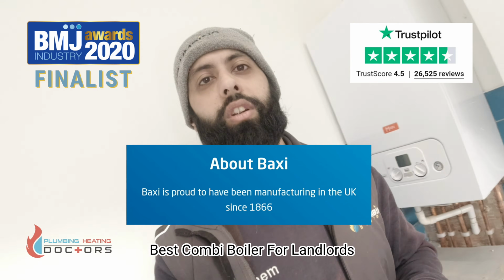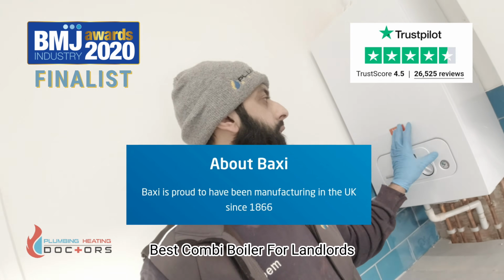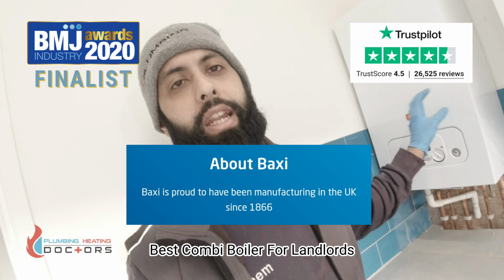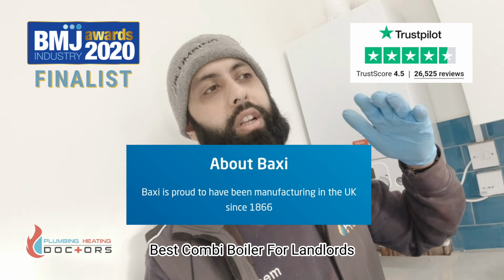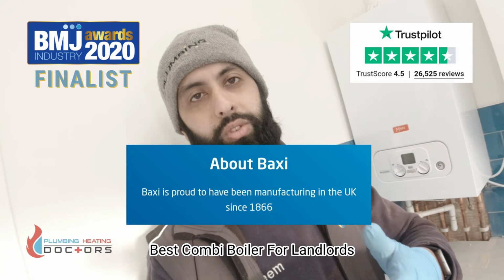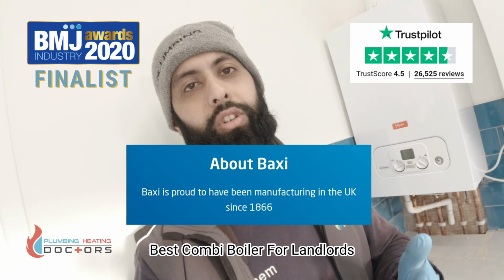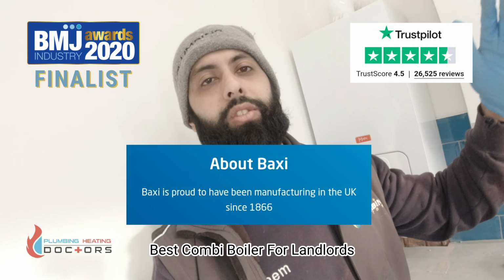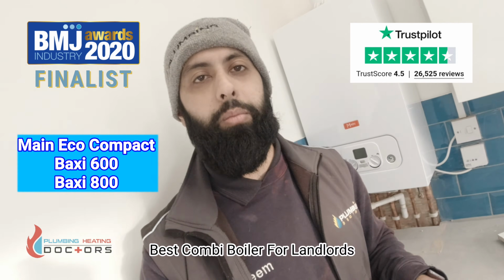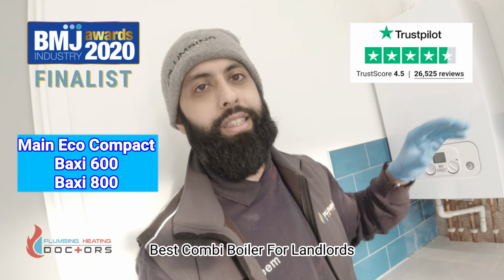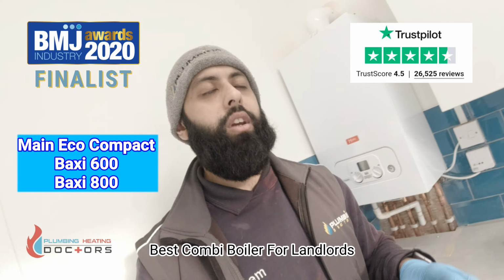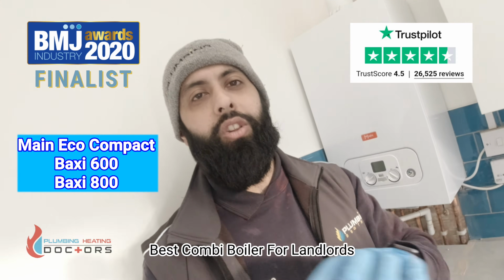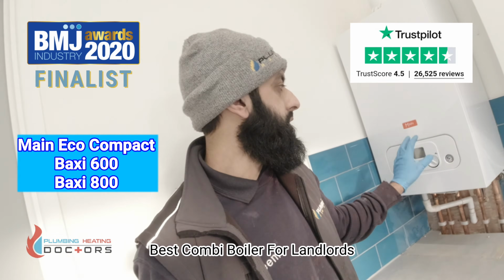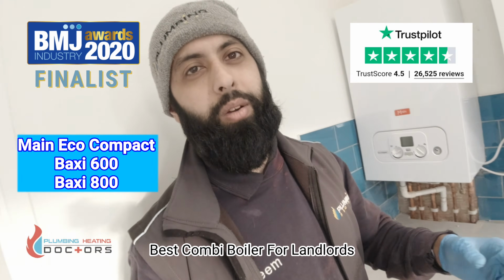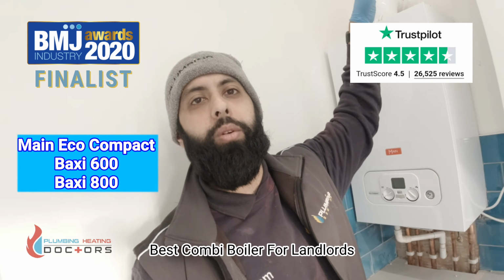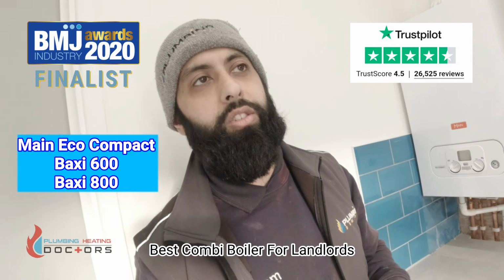All they've literally done is made this boiler into 3 different variants. They have the Main Eco Compact, targeted towards the lower end for landlords and so on, then the Baxi 600, and the Baxi 800. They're exactly the same boiler inside as the Baxi 800 and Baxi 600. The only differences are minor things like the badges and the filling loops. At the back of these boilers you can't rear pipe it, whereas with the Baxi 800s and 600s you can.